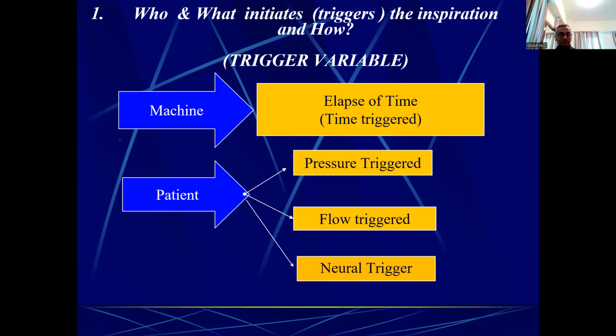Okay, now these are all happening after the flow starts. Now, how good it will be if we can sense when the medulla oblongata of the patient starts thinking of giving a breath. There is a trigger from the medulla oblongata, and that is sensed by the machine, which gives a breath, rather than that signal going to the diaphragm, contracting, causing negative pressure in the pleura, and that causing the flow into the ventilator, which is sensed by the machine to give a breath. That is a whole big route. Instead of that, if we pick up the signal from the medulla oblongata and sense it and give a breath, that is called neural trigger.